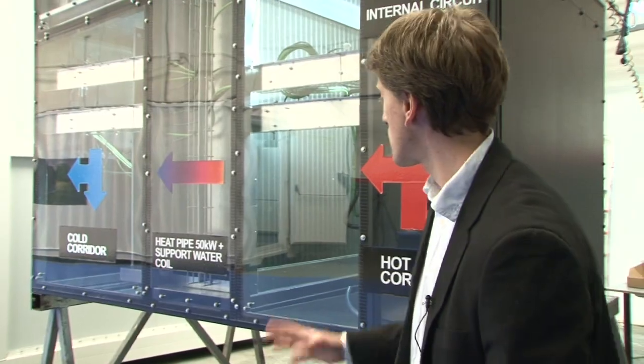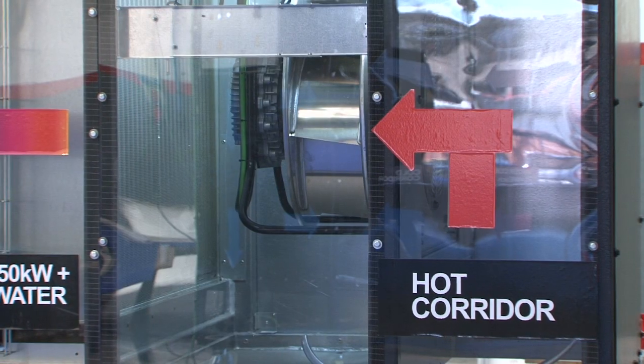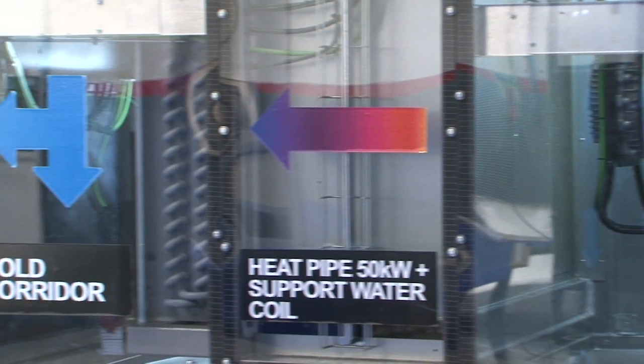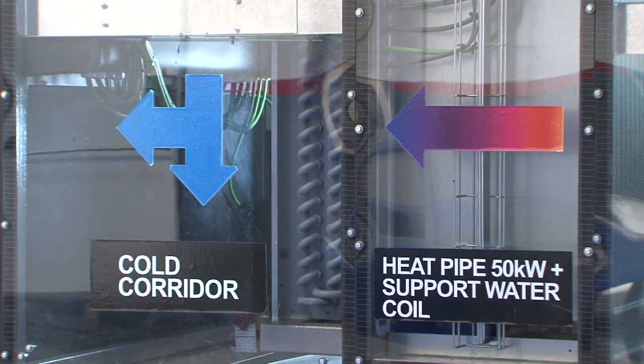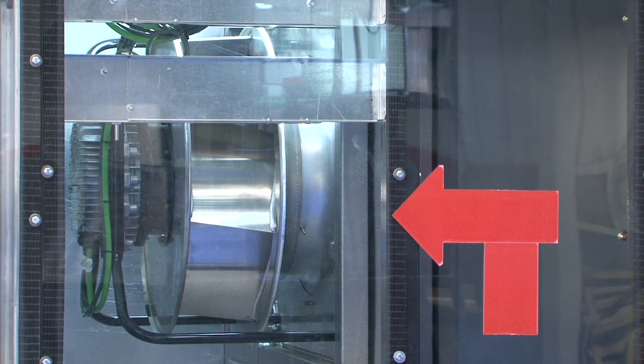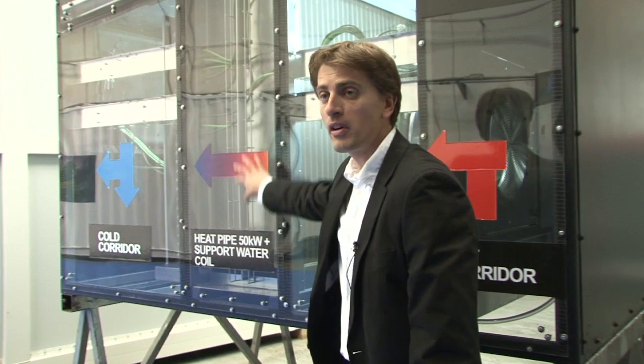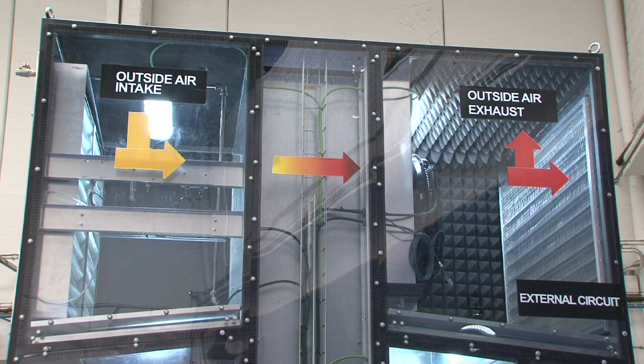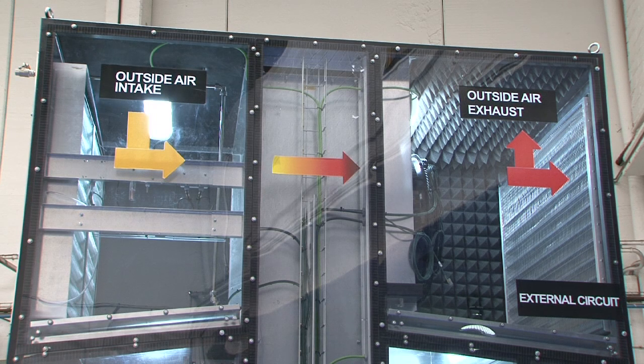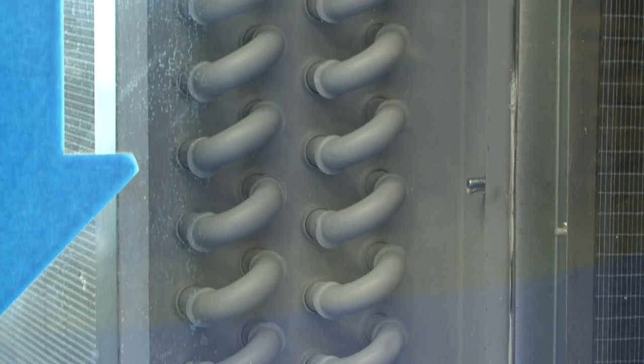How the unit works is that it captures the air from the hot corridor or from the plenum of the data center towards the air-to-air exchanger or the air-to-air economizer, which is crossing external air towards the top side and lowers the temperature again on the cold corridor side of the unit.